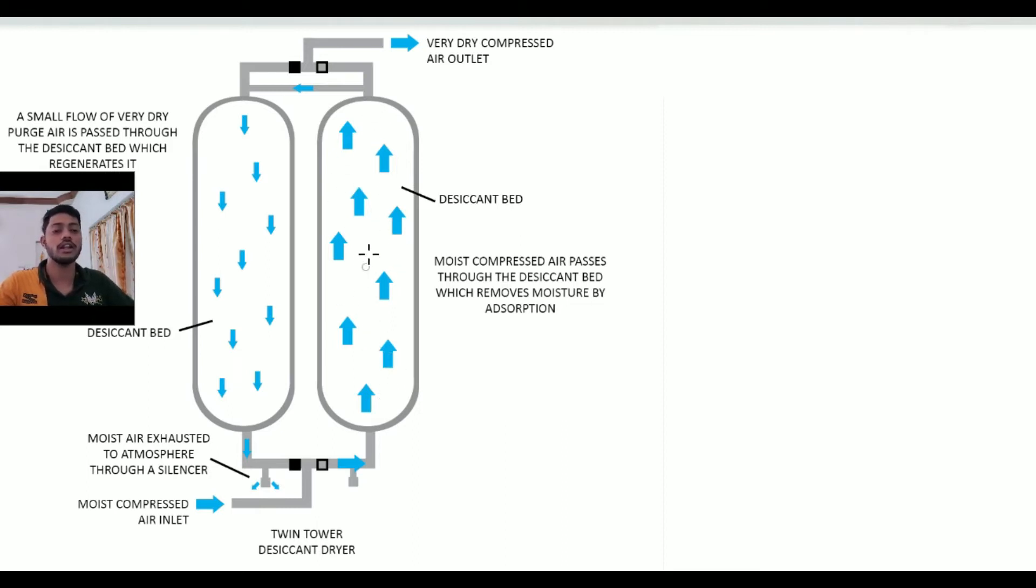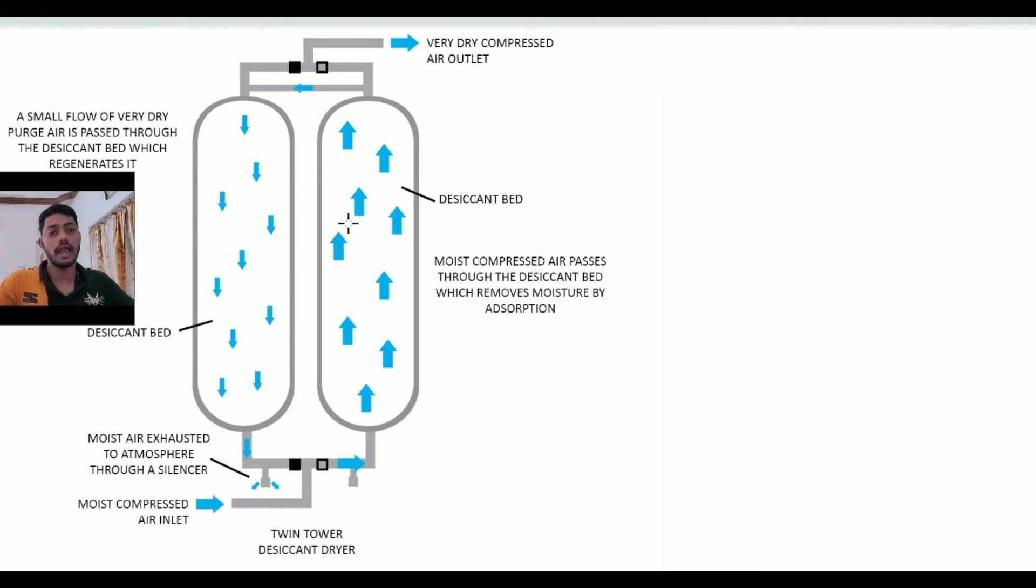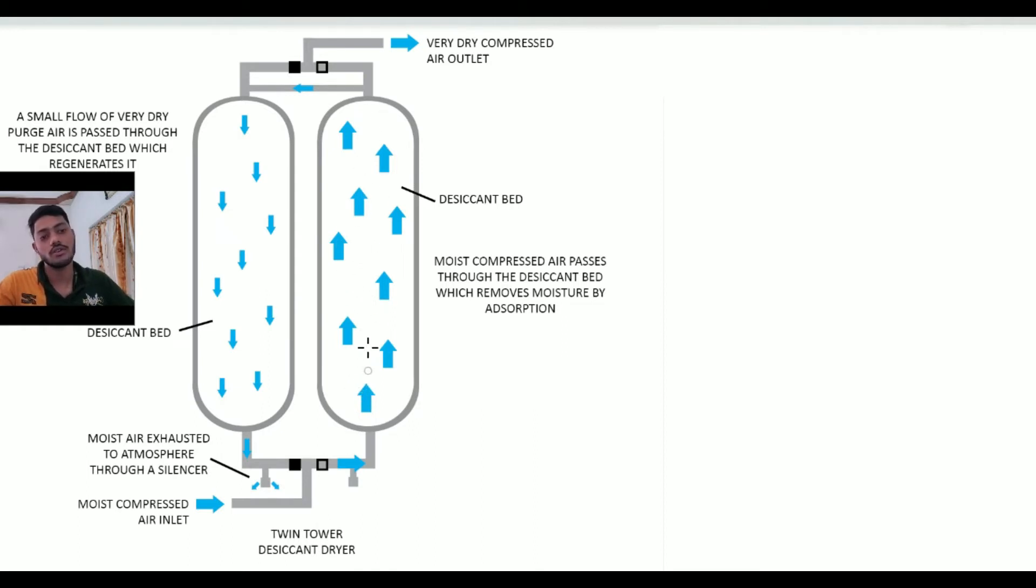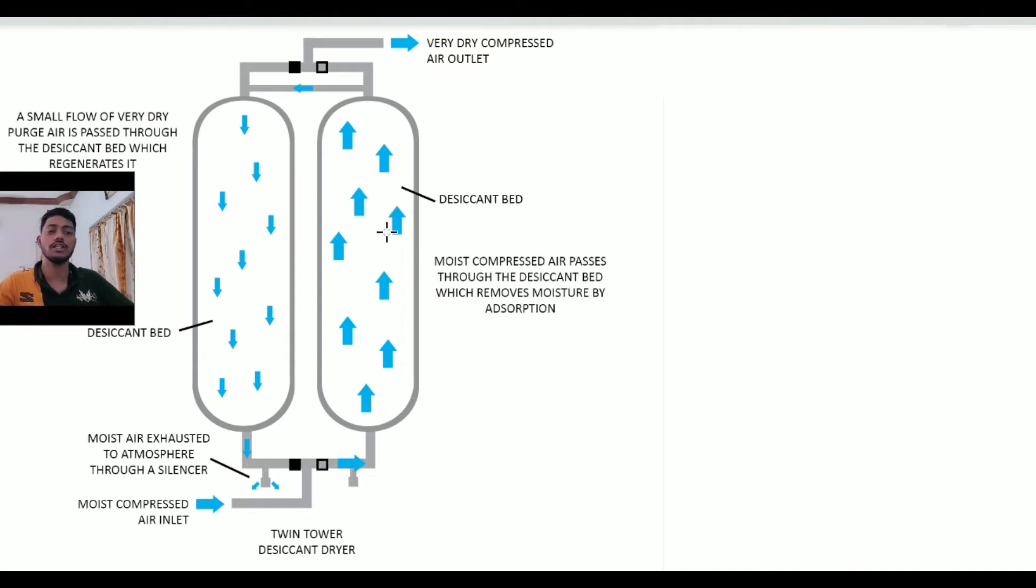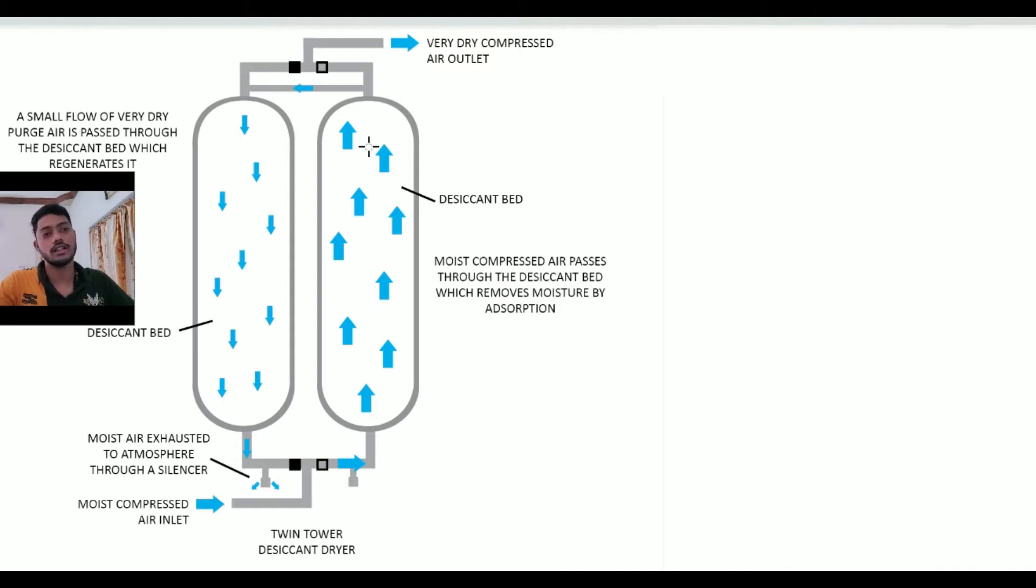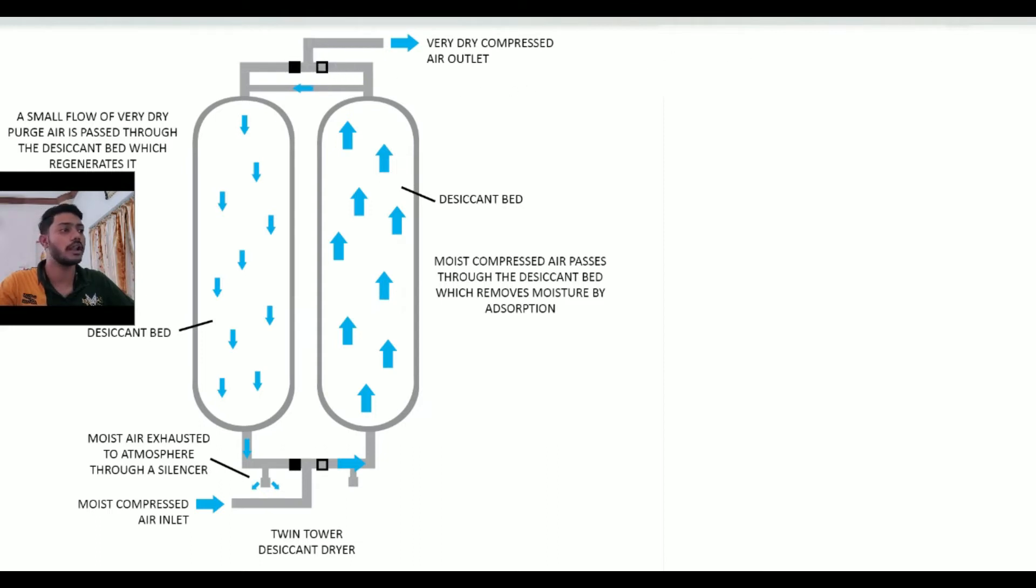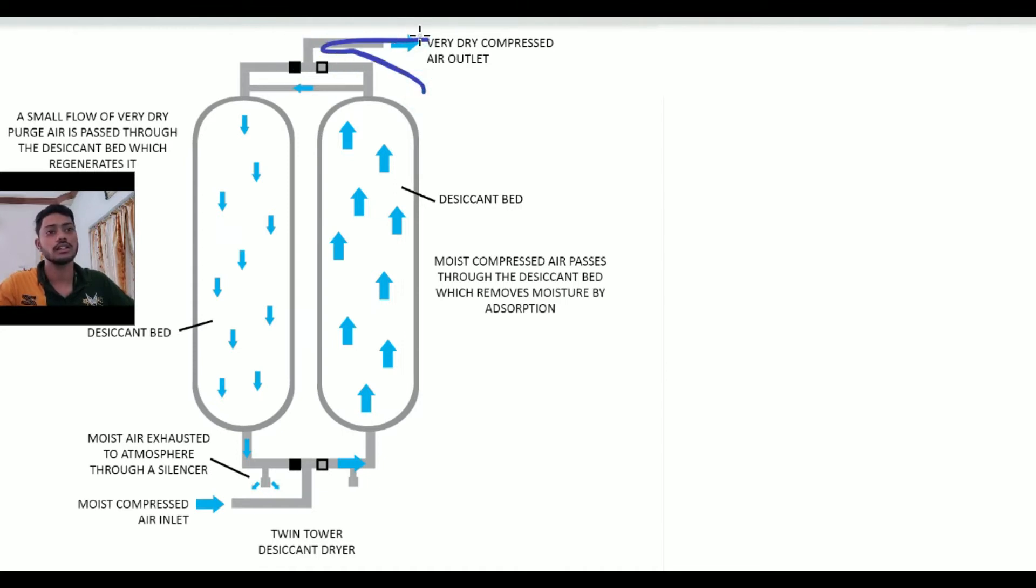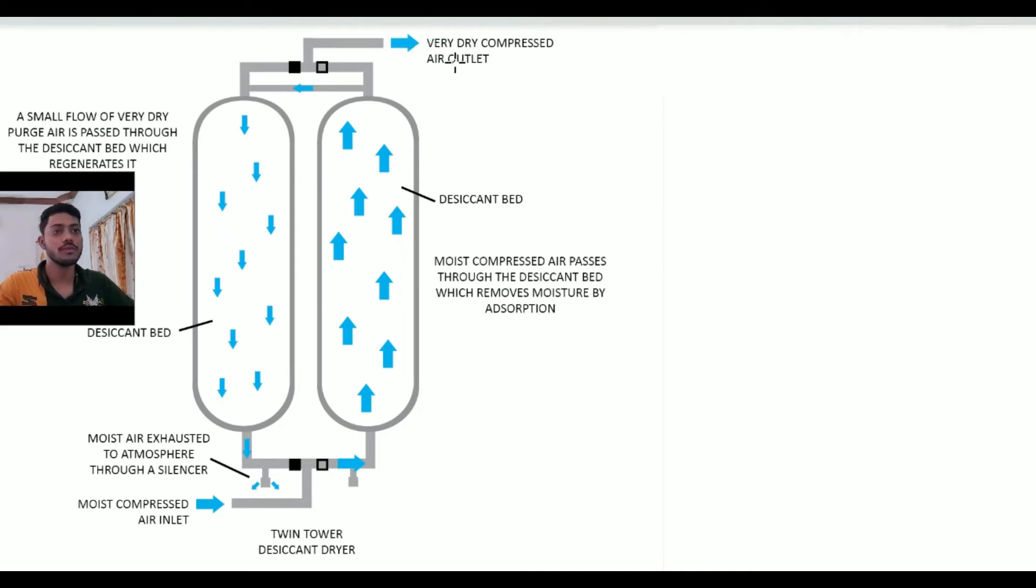The air is passing through the desiccant balls or molecules, and the desiccant has the property to absorb air moisture. As the air passes from bottom to upward, it gets dry and the air moisture is absorbed by the desiccant molecules. Then the dry air comes out from the top portion outlet line, and you can see this valve is open.